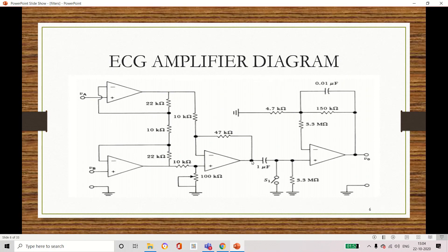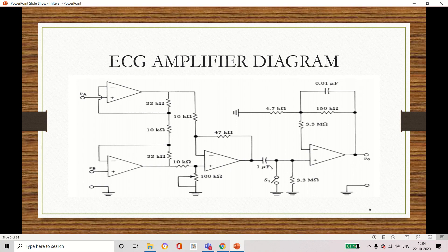This is the output of the instrumentation amplifier. Along with this we are adding an additional circuit, so this circuit diagram is called the ECG amplifier. Here we have a CR combination: capacitor value 1 microfarad and resistance value 3.3 mega ohm. We also use one switch, which automatically closes when the output is saturating, reducing the discharging time constant. At the feedback side we have a resistor and capacitor, plus additional resistors of 3.3 and 4.7 kilo ohm.